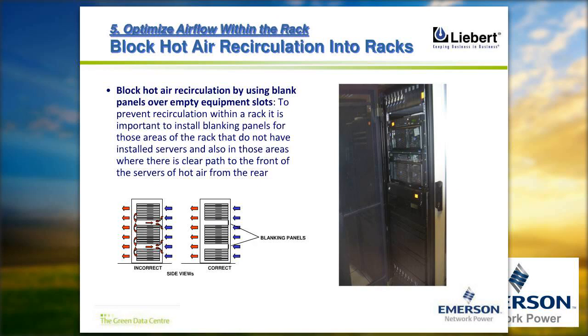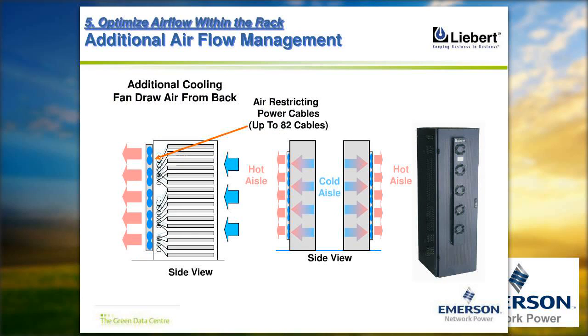If you look at your data center, many a time you get into an issue of recirculation of hot and cold air. There is a gap between two servers where hot air gets mixed with cold air, and that can be avoided by putting blanking panels properly. So these are all very small tips which will improve energy consumption and reduce your operating costs. Many of these are low hanging fruits which you can start even doing from tomorrow, and as you move forward, all the strategies can be adopted over a period of time.